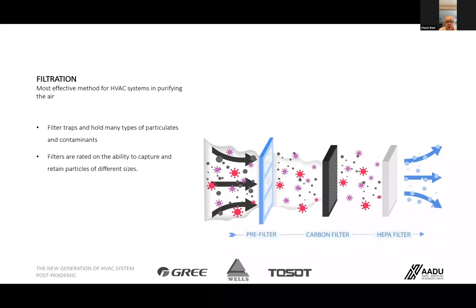Next. As we see here, more equipment nowadays is not coming through with just a simple filter rack. We're adding additional filter racks so we're able to control the amount of viruses or bacteria that we have. We have a pre-filter, normally a MERV 6 or 8, which will remove about 50%. Then we can add a MERV 13 to 16, which will reduce anywhere from 85 to 95%. And then we could finally finish this off with a HEPA filter, which removes about 99% of any particles or contaminants in the air.